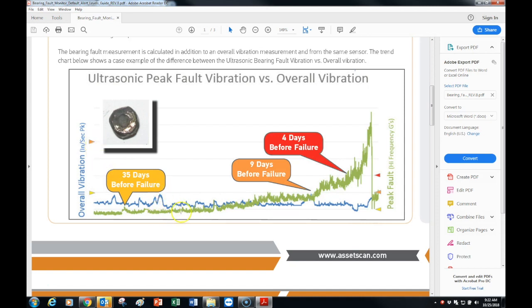And the green line is the ultrasonic measurement, it's a high frequency vibration that's contact based ultrasonic that is 1000 to 25,000 hertz, and its units of G's. The alert limits are set at 6, 12, and 18 G's.